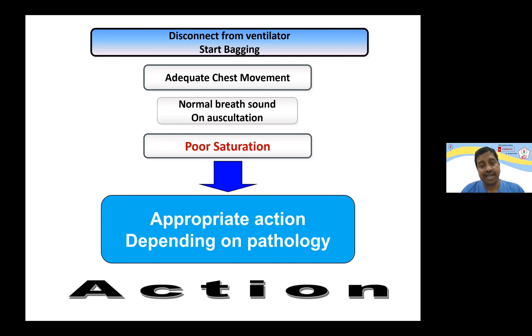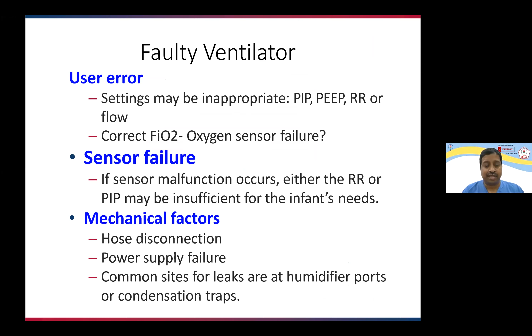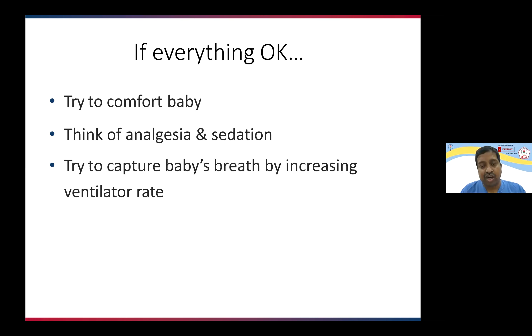A faulty ventilator could be due to user error, a sensor failure or mechanical factors, that is, obstruction in the hose pipe or power supply failure. If everything is okay, then try to comfort the baby and think of analgesia and sedation, because it might be due to pain or asynchrony with a spontaneously breathing baby. Try to capture the baby's breaths by increasing the ventilator rate. Suppose the baby is breathing at 55 and you are keeping the rate at 30, then a lot of asynchrony can happen. So just by increasing the rate, sometimes the events can decrease.